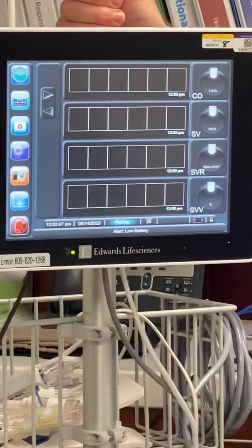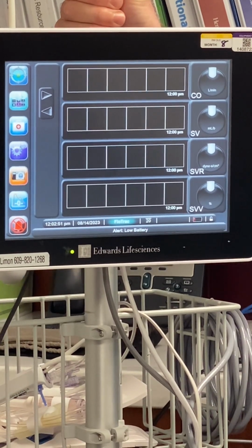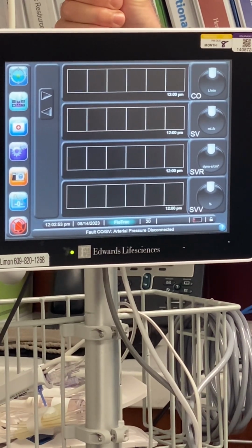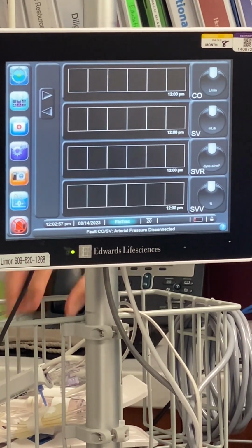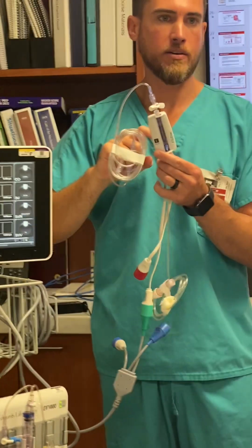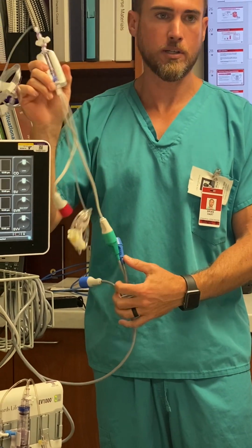Now, when we used to have the LiDCO, a patient had his own card. Does this utilize one? You don't need cards. Nope, that's the beauty of this. It's non-calibrated and you don't need the cards. So how is the data saved? It actually has a USB in here where it can save the patient's data for up to 96 hours, I believe.